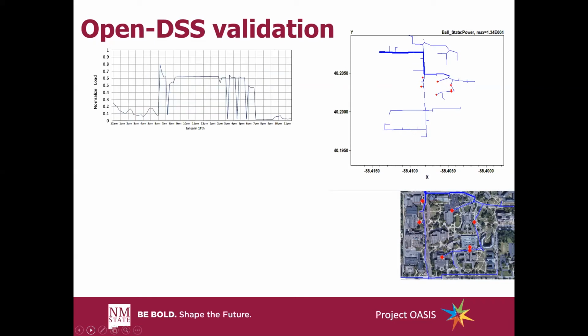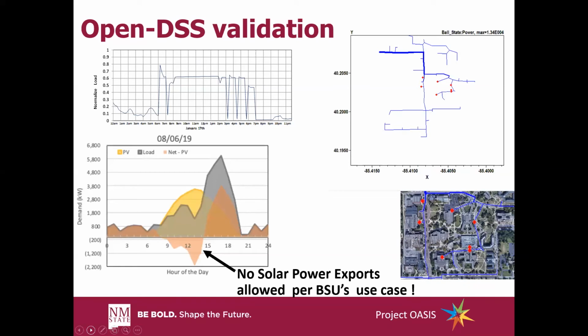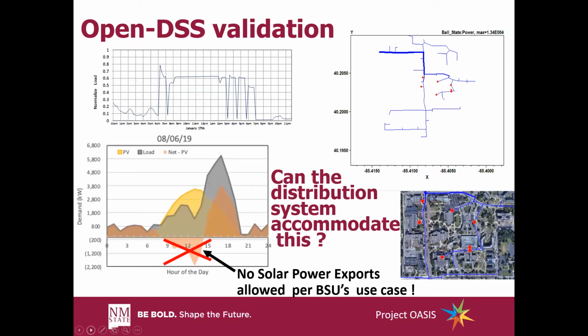We realized that the campus load provided in the use case showed extreme load drop-offs to less than 5% of total load, even during business hours. While this may not be a realistic situation in real life, this is exactly when PV power will be exported. Since no power export was one of the primary conditions for our use case, our next challenge was to size and rate the battery system, which would mitigate this.